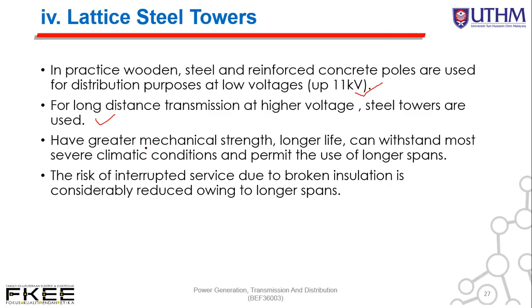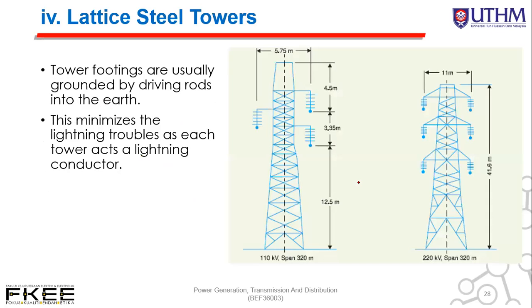And then they have great mechanical strength, longer life, can withstand most severe climatic conditions and permit the use of longer spans. The risk of interrupted service due to broken insulation is considerably reduced owing to their longer span. Okay, this is contoh of the lattice steel tower. Ada dua bahagian. Yang pertama untuk 110 kV, okay, span 320 meter, and then 220 kV, span 320 meter.